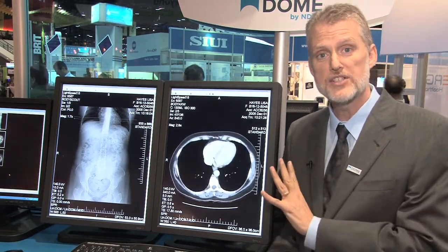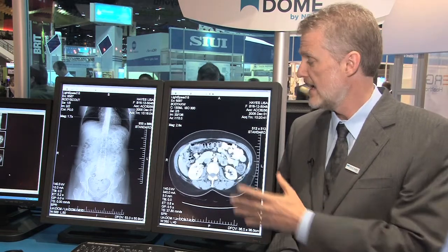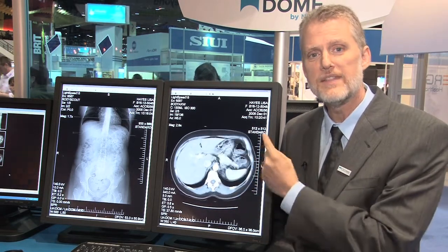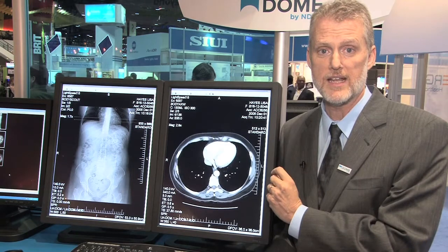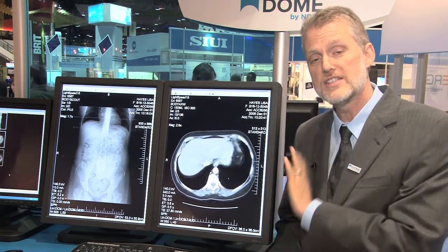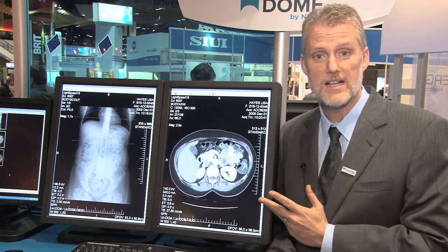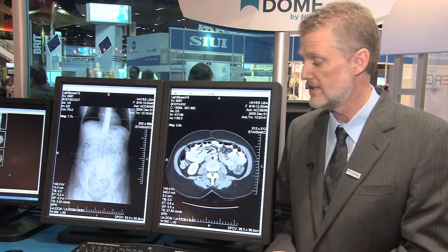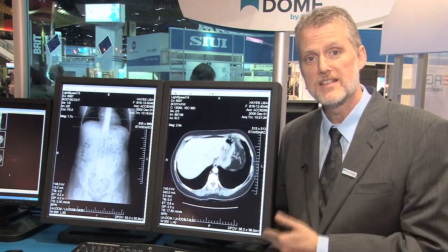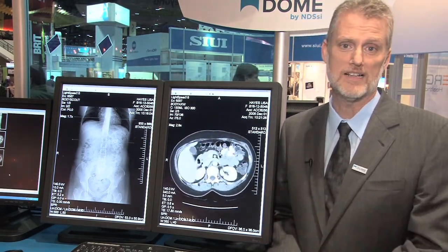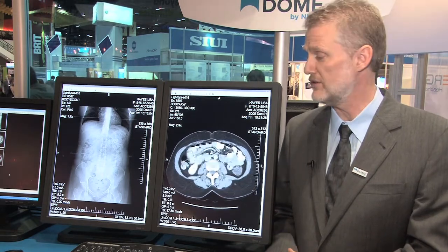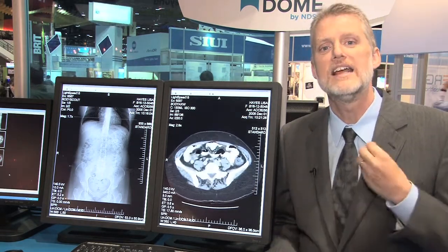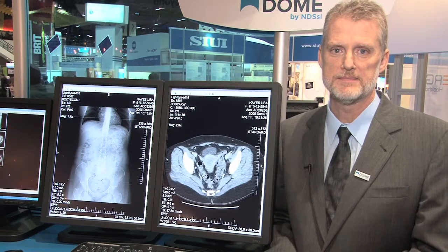There we use a high-precision, traceable photometer in a carefully controlled environment to get the most precise DICOM measurements we can. That characterization is then stored in the flat panel, along with the DICOM lookup tables for our calibration. So when the display ships, it is absolutely perfect DICOM out of the box and ready for your use. The question is, how will it perform over time?